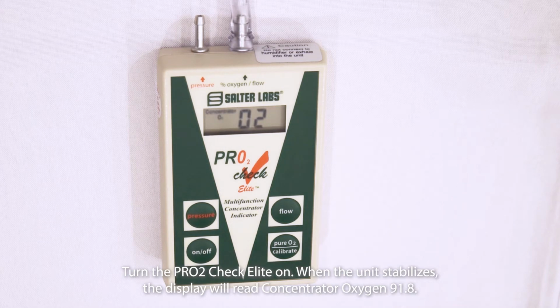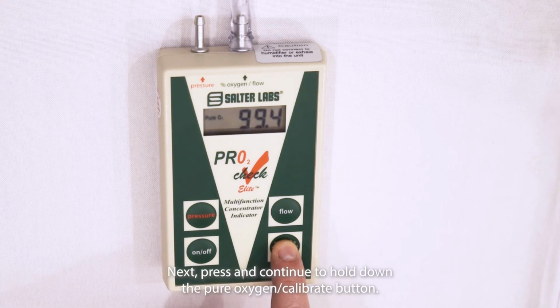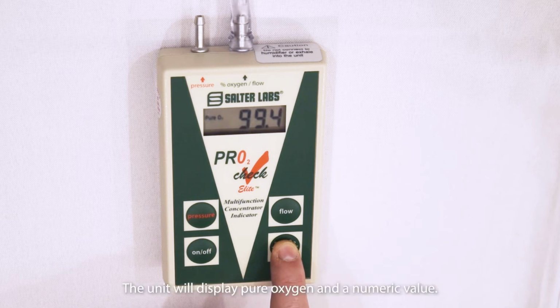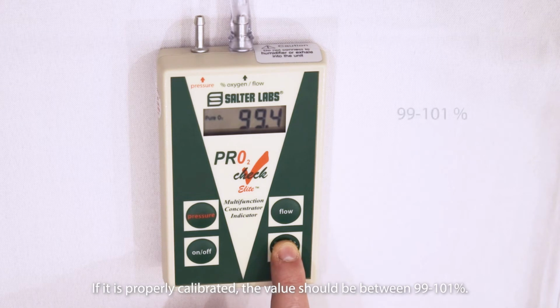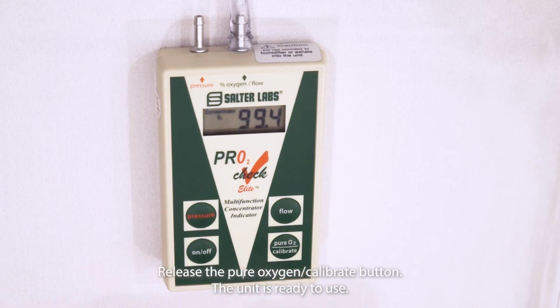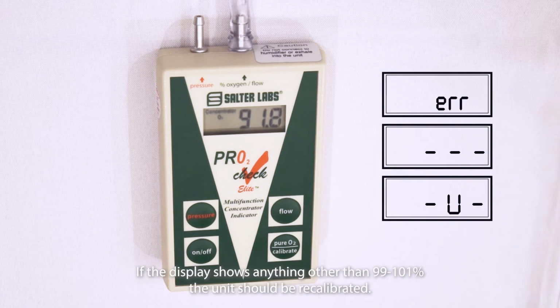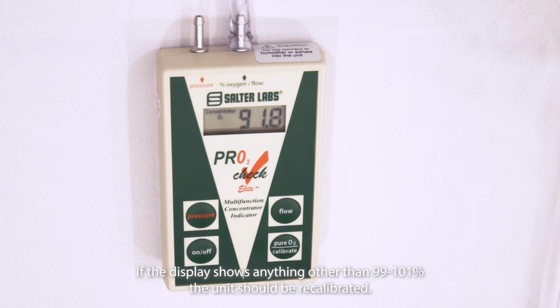When the unit stabilizes, the display will read concentrator oxygen 91.8. Next, press and continue to hold down the Pure Oxygen Calibrate button. The unit will display pure oxygen and a numeric value. If it is properly calibrated, the value should be between 99 and 101%. Release the Pure Oxygen Calibrate button. The unit is ready to use. If the display shows anything other than 99 to 101%, the unit should be recalibrated.